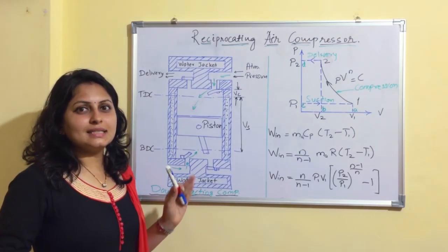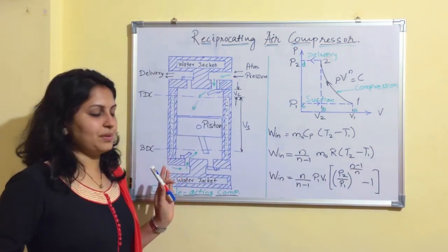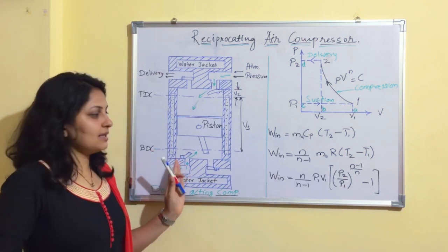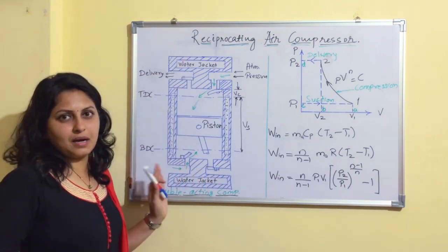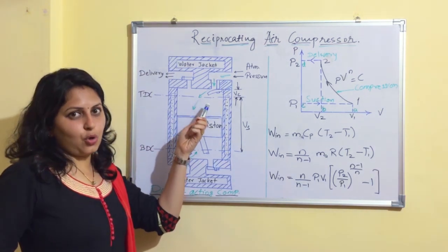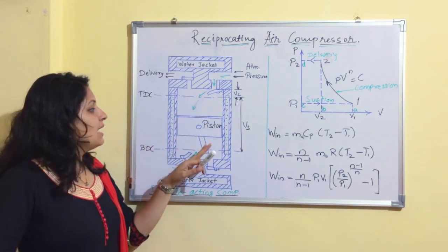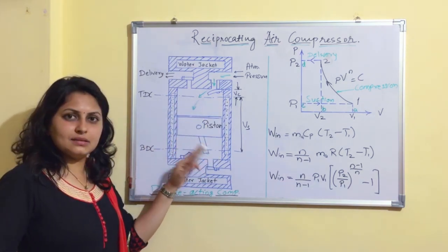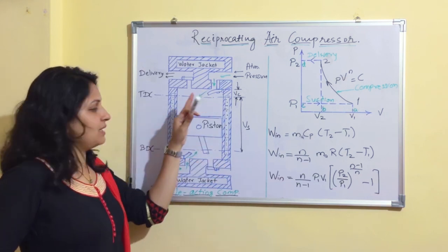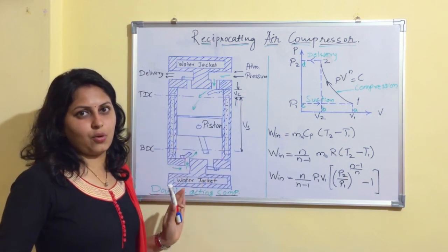Now let us take a look at the double acting compressor. The arrangement is the same as the single acting compressor, but with an additional inlet valve and delivery valve at the opposite end. As the piston moves from top dead center to bottom dead center, suction takes place on one side while compression and delivery occur on the other side. When the piston moves from bottom dead center to top dead center, the process reverses. This is the working of a double acting compressor.